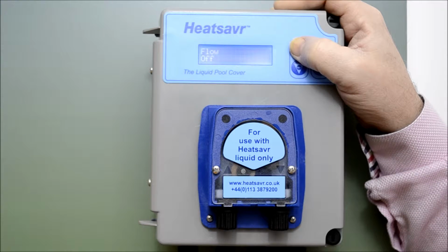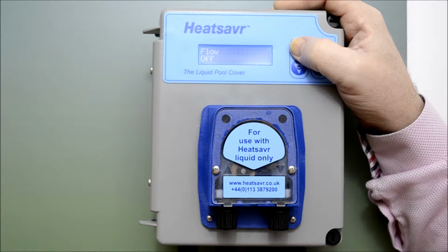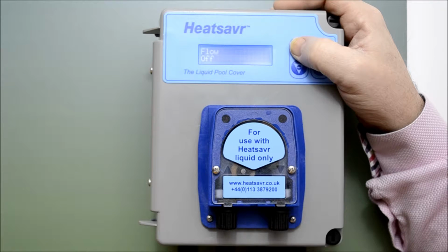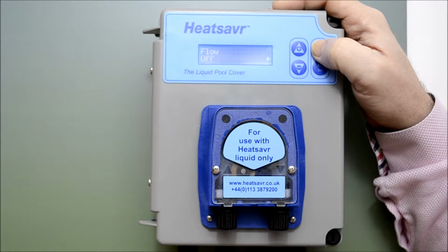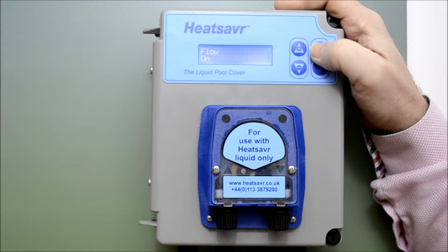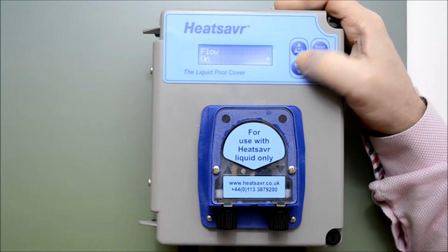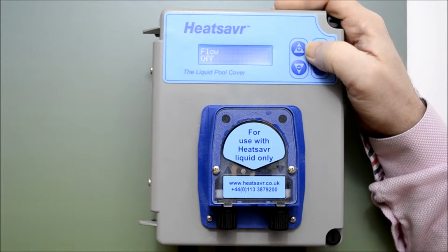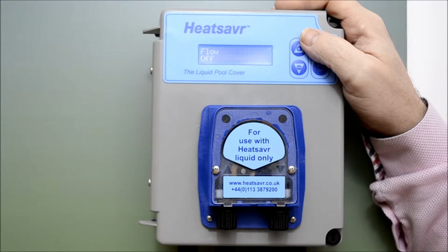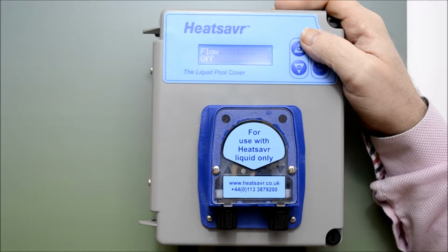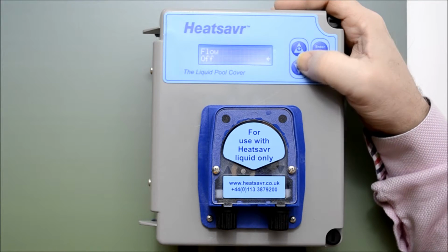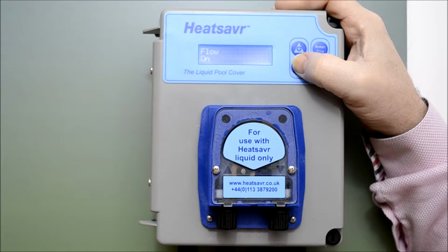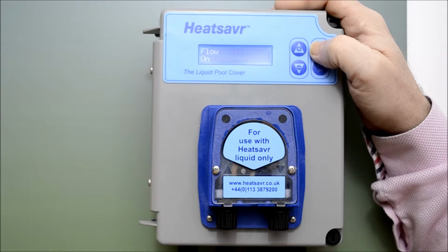The next screen is flow. This is again optional, but gives the end user the function of inhibiting dosing should the circulation pump be turned off. Initiating this feature will require a qualified professional as it requires an electrical connection. The mains live supply to the circulation pump will need to be run through the terminal block marked flow on the printed circuit board. To initiate the flow function on the display, press enter and then use the up or down buttons to select. Press enter to confirm.